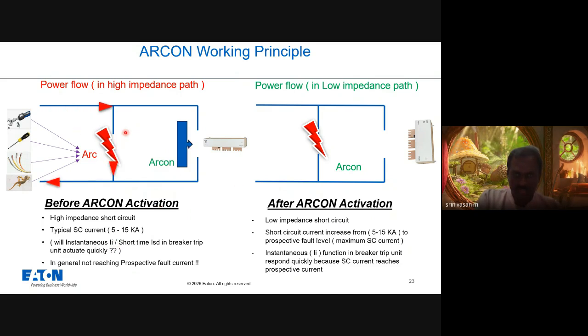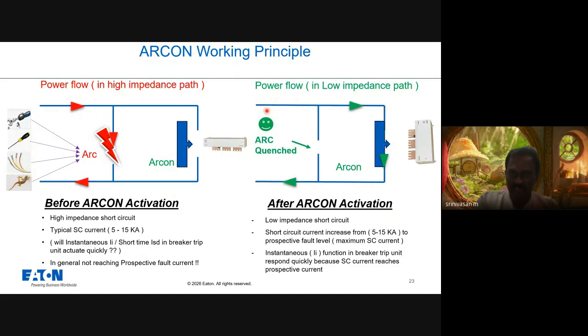once the internal arc is happening, this ARCON or quenching device will be activated, which I will explain in the next slide. That will create a parallel low impedance short circuit. Earlier, the short circuit energy was flowing through this path. Now, parallel to that one, we have a low impedance path. The current has a tendency to flow towards the low impedance path, so the energy which was flowing through the arc path is cut off, and the arc is getting quenched.